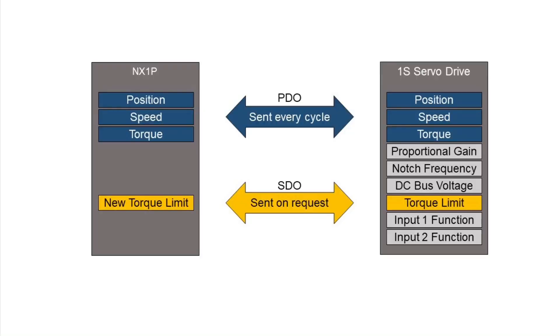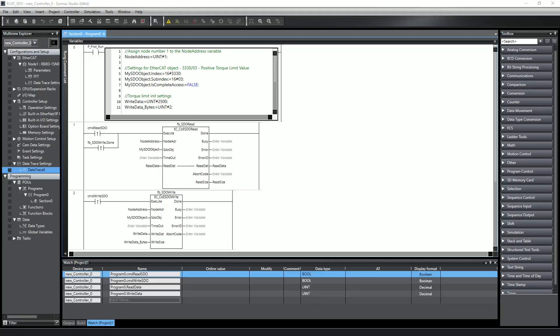User manuals for EtherCAT devices will tell you if an object can or cannot be accessed as a PDO. Objects that are accessed infrequently are known as service data objects, or SDOs, and these are accessed on an as-needed basis using specific read and write commands. SDOs can make your system extremely agile because they allow you to make changes on the fly. They also allow you to create parameter backup files or even have parameter changes directly from the HMI, so you don't need to bring out another setup software to make device changes.